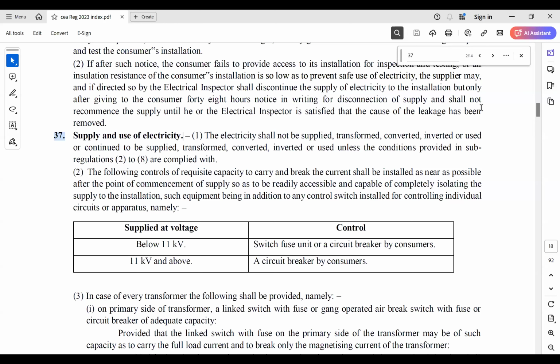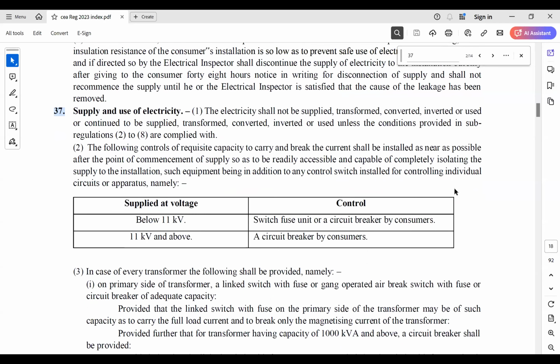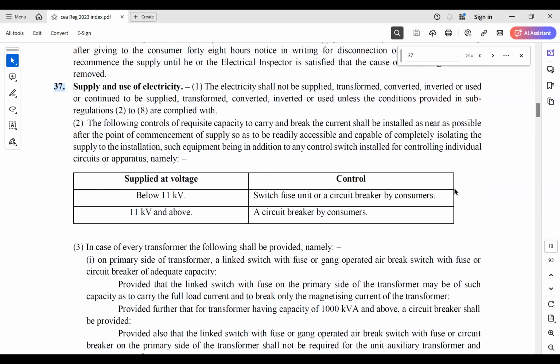On the other hand, when they go into the 11 kV and above voltage level, that is 11, 22 and 33 kV, they have mandated a circuit breaker by the consumers. Now, earlier what used to happen at ground is that above 1000 kVA, it was mandatory for the consumer to provide a breaker before the transformer.